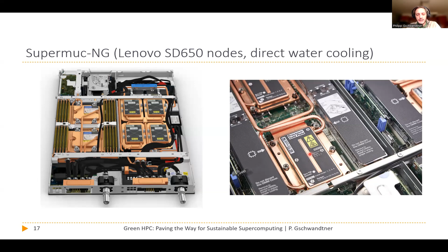On the slide, through the video stream it's probably a little bit too small to read, but here, for example, you have one of the cooling devices for the CPU, and it tells you it has 4 screws, in what order to tighten them, and it also tells you what torque to use: specifically 1.4 to 1.6 Newton-meters, which is the amount of force to tighten the screws with. If it's less than that or more than that, it's out of spec and you're out of warranty, which shows you the tolerances in these systems, because you have water flowing through this thing, you really need to adhere to the spec.